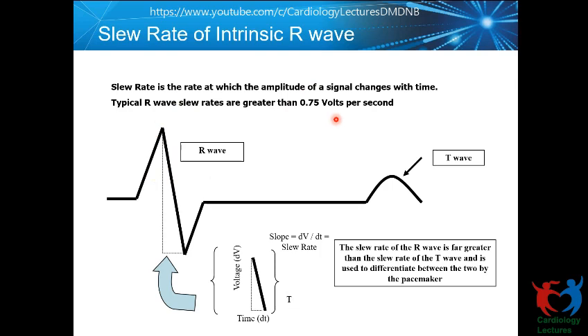But at the time of implantation, it is worthwhile noting that value. Typically, when you get a good R wave, the slew rate is also higher. For an R wave, the good slew rate should be 0.75 volts per second. How frequently it's changing, that's what it is. So for a P wave, it should be more than 0.5 volts per second. In case you get a reasonably good R wave, and then let's say only about 0.4 volts per second as a slew rate, you may want to reposition it at that time.